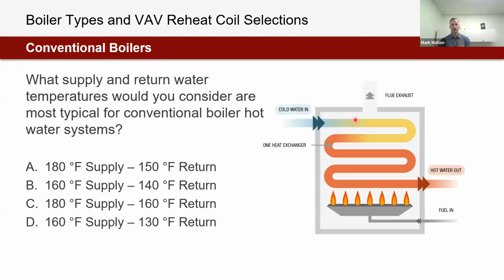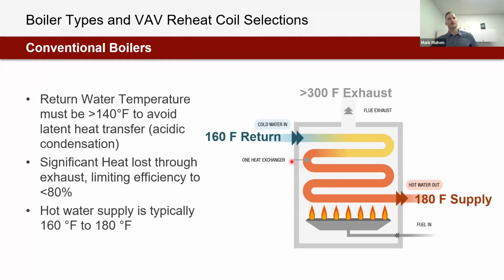So with that being said, the first thing I want to discuss is conventional boilers. And I like to address this one with a question. So I'm going to ruin the Q&A chat for a moment here. The quiz question is, what supply and return water temperatures would you consider most typical for conventional boilers? Answer right into the chat or the Q&A section. We have items A, B, C, and D here. What do you typically see as most common if we're looking at a conventional natural gas boiler? I already have a couple of answers rolling in here. 180/150 or 180/160 is generally what we're seeing. So Jason, Heidi, Tyler, thank you. Everyone's kind of agreeing that A and C generally are what's most common. I agree. So 100% answer so far from everybody.